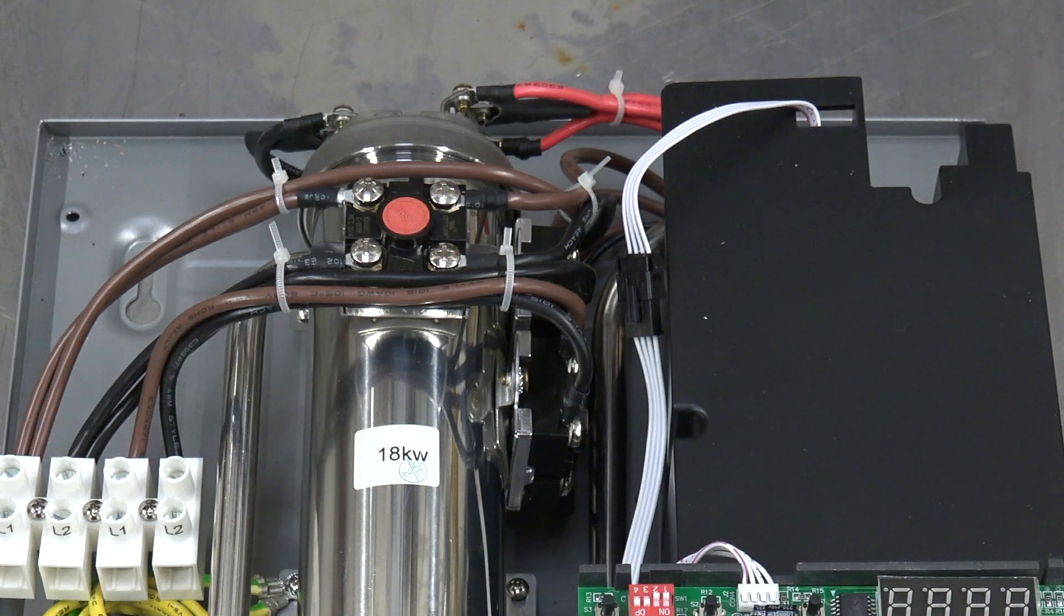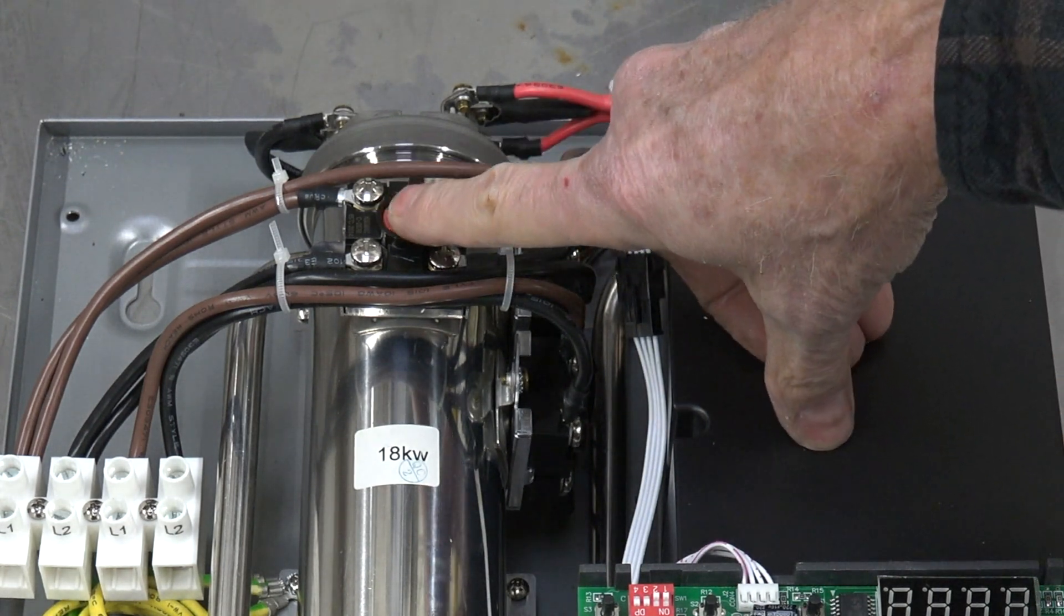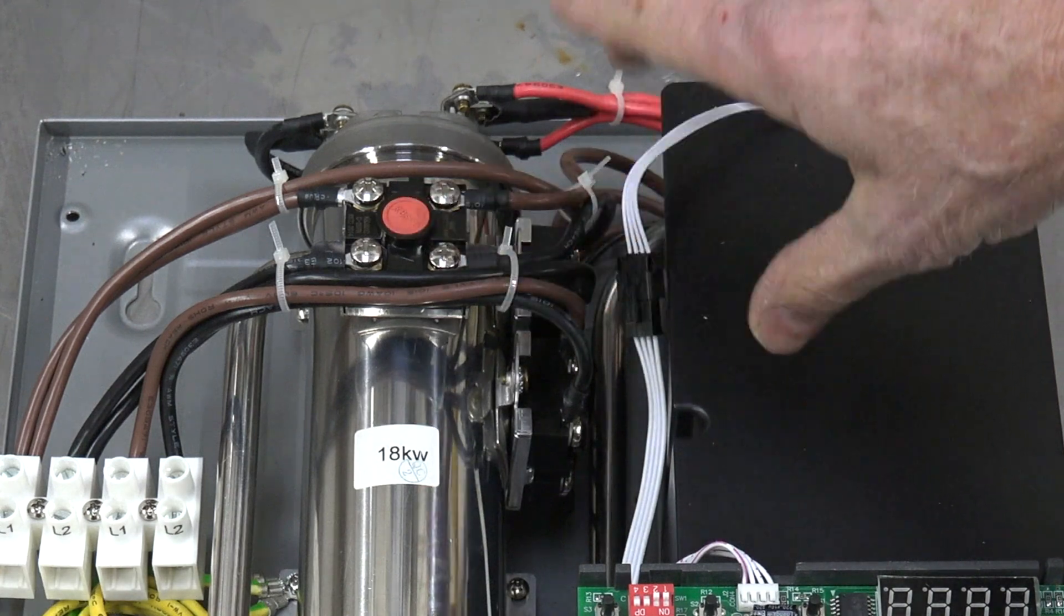What those are for is if an element burns out, that doesn't mean it stops heating. Depending on how much resistance there is in the water, and if it has actually burned through the metal casing of the element, it may continue to heat - maybe not near as much, but it will still heat. So you have these ECOs, energy cutout, in case something like that happens because it cuts all power to it.